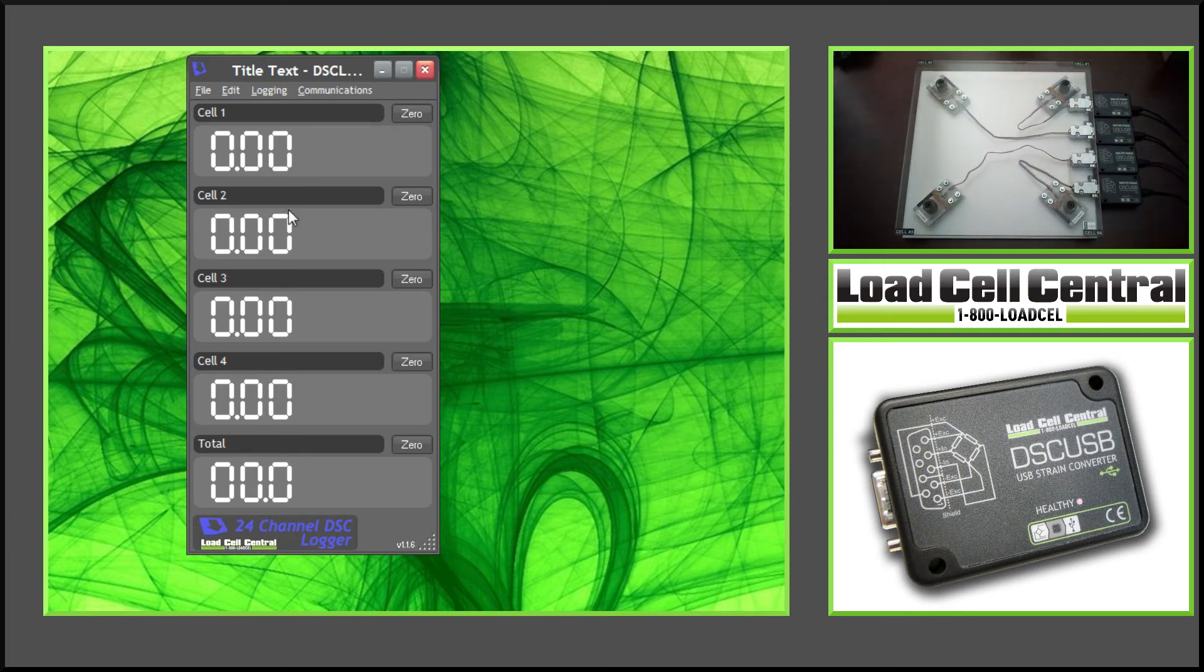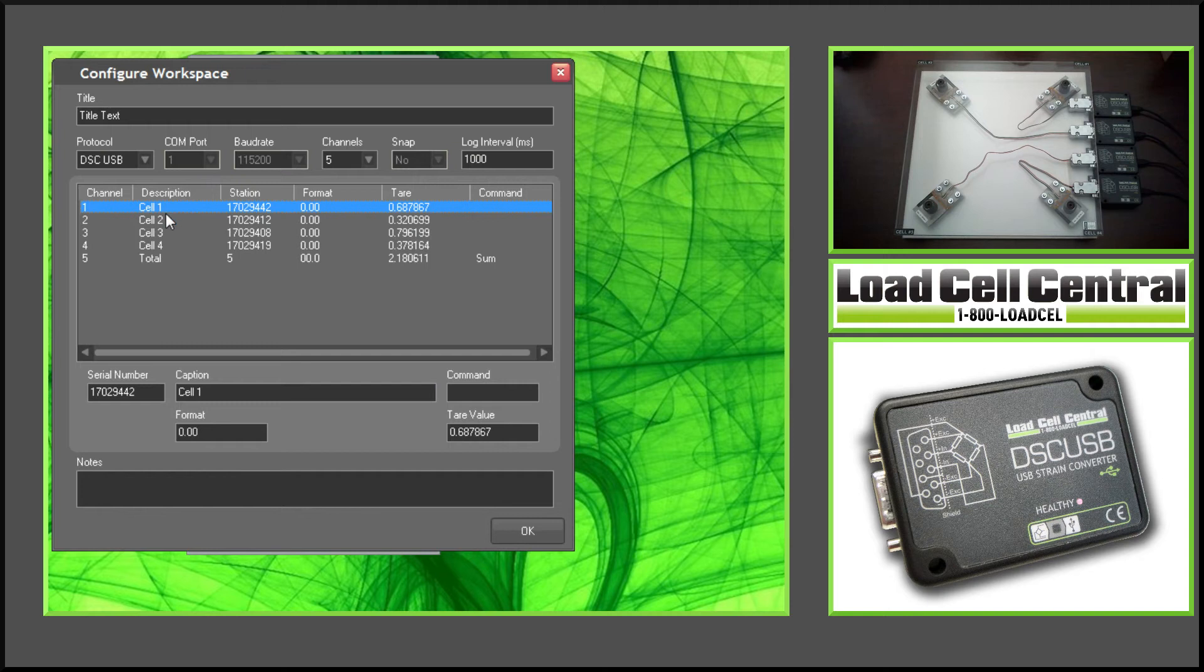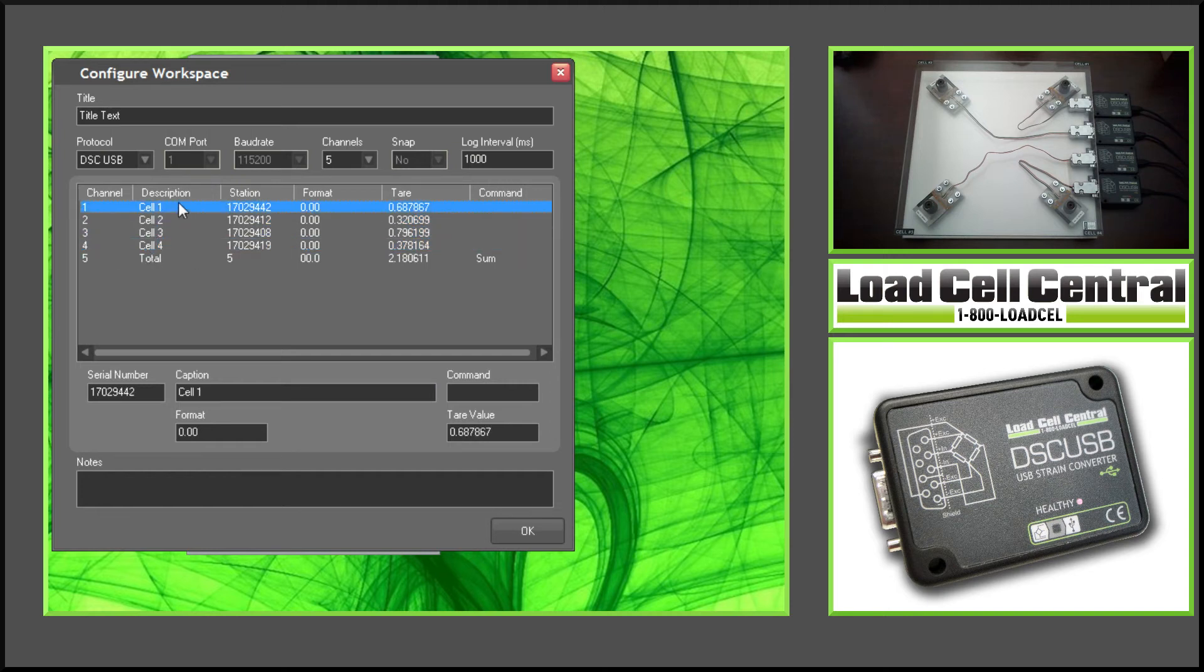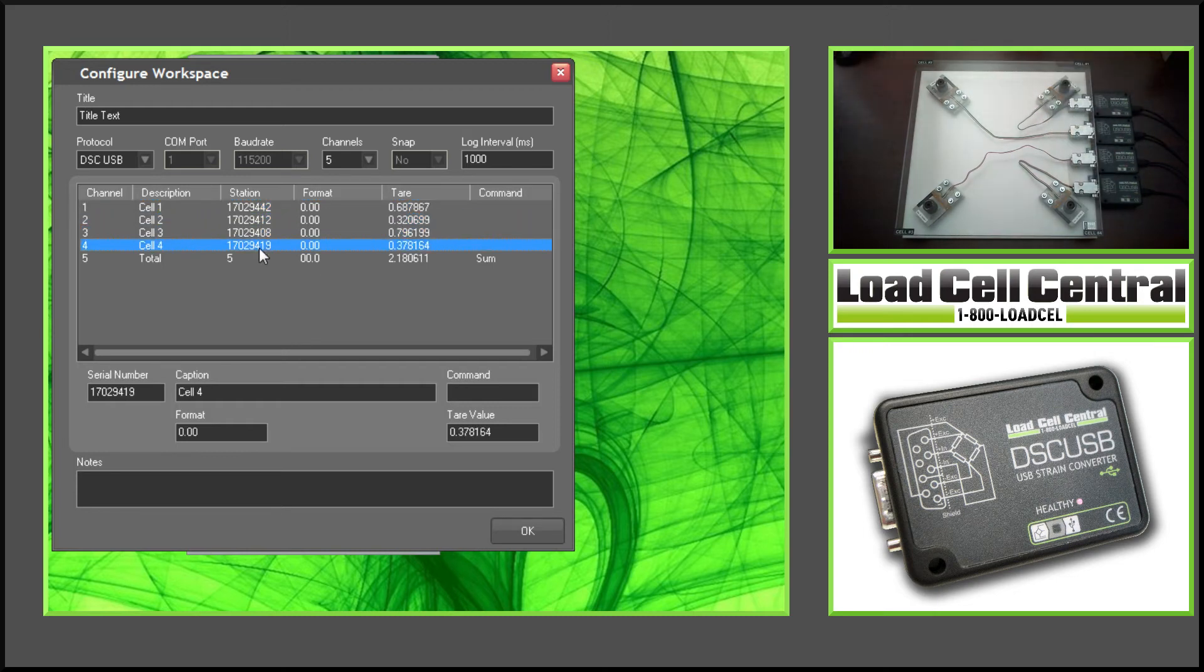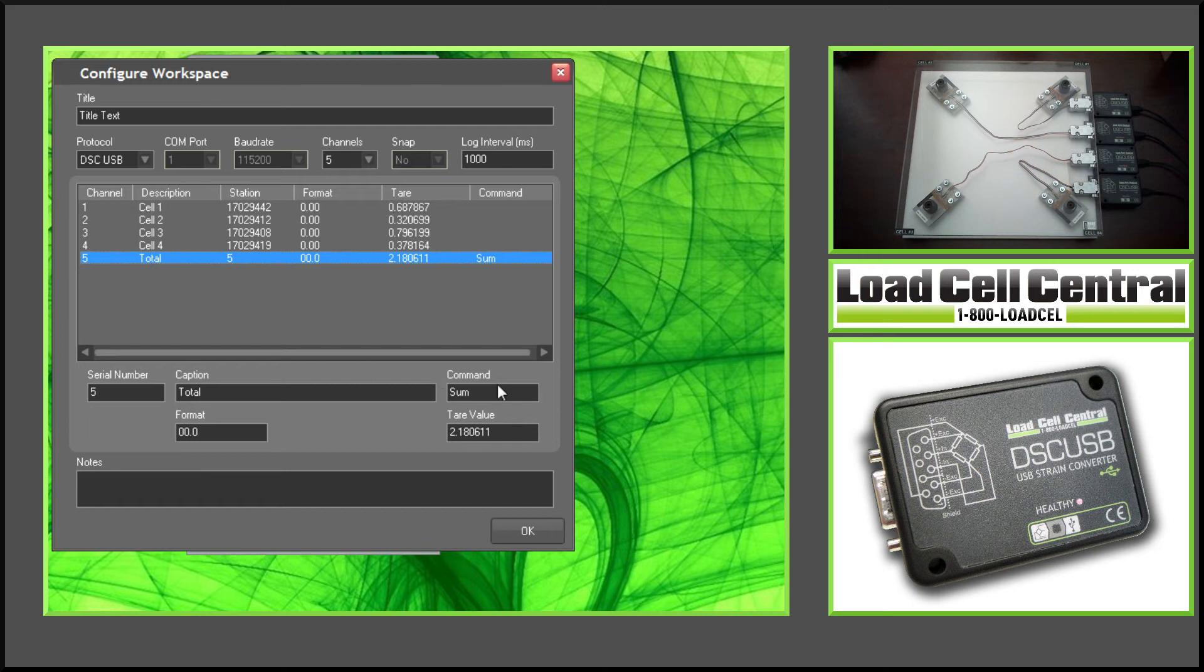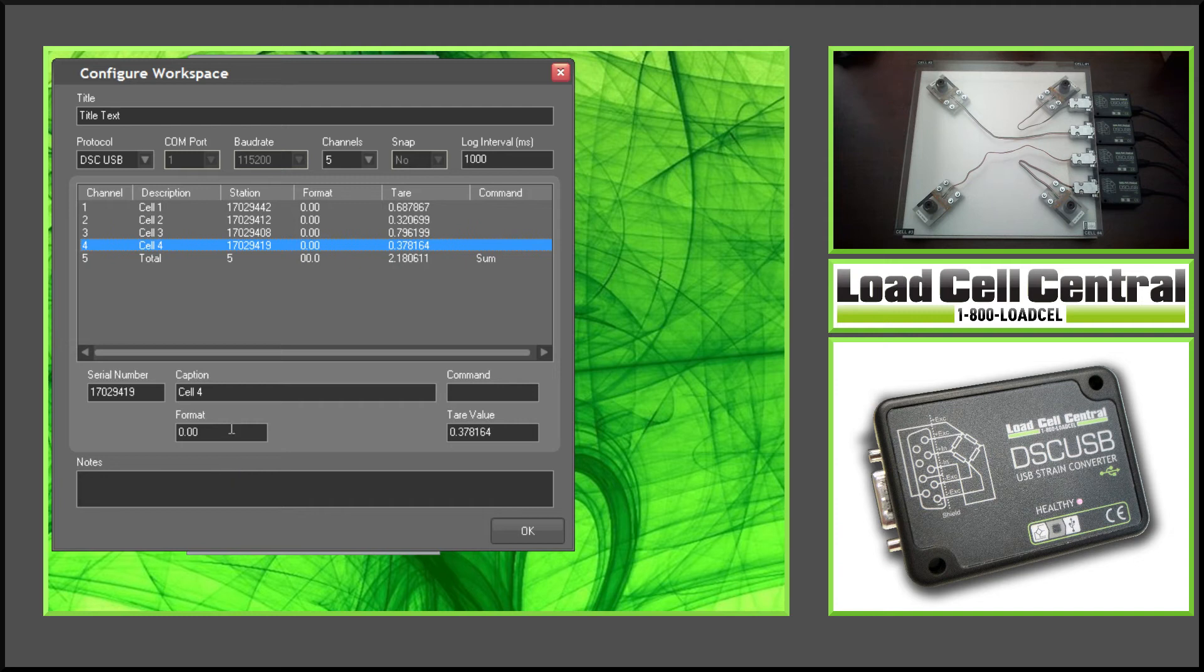I have cell 1, 2, 3, and 4. I also have the total, or the sum, of these cells. If we take a look at the workspace, we can see each cell 1, 2, 3, and 4, the channel number. These are specified by the serial numbers of the DSC-USB modules. Channel 5 is using the SUM command to sum all of the other channels. We can also change the format, the tare value, as well as whatever we would like to call that channel.